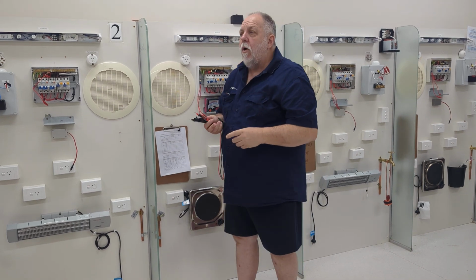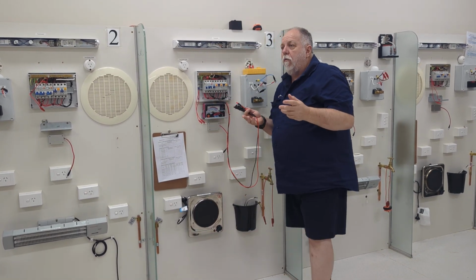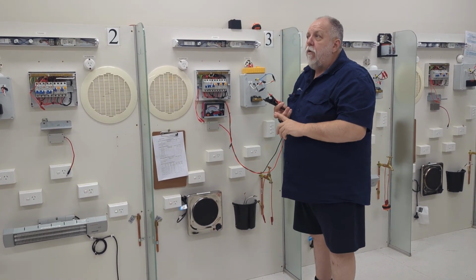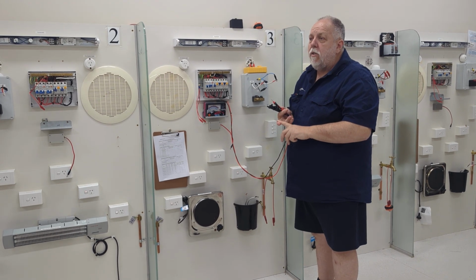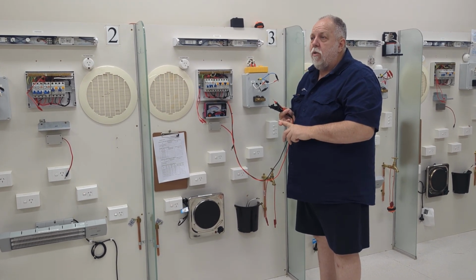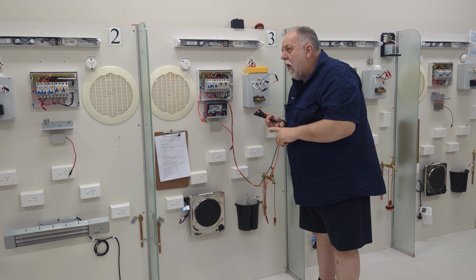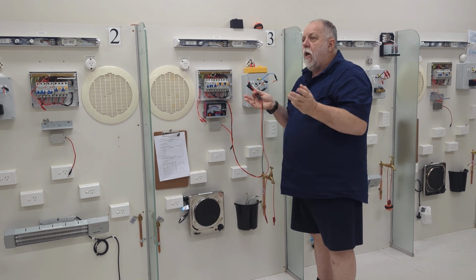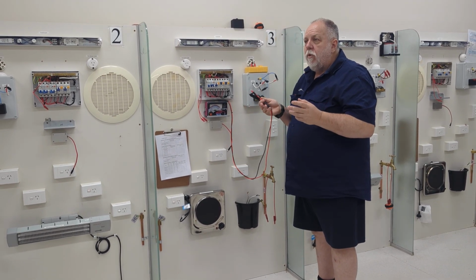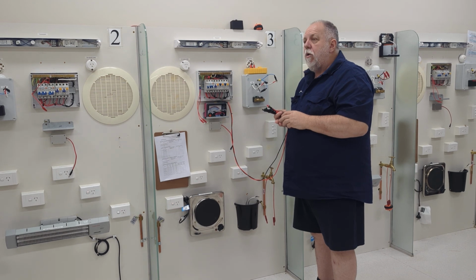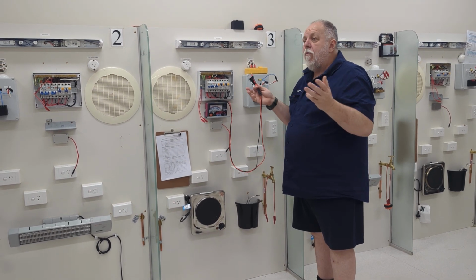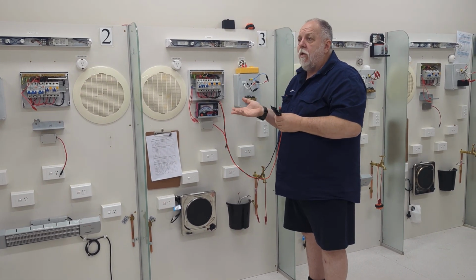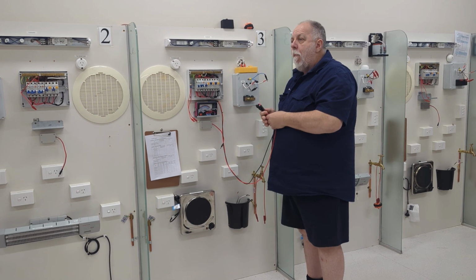Things that could also be in a lighting circuit is what? What other faults could I have? If you've got fluoros with ballasts and capacitors, they're ones that create shorts. Most LED lights these days, they don't normally create a short, they just go open circuit or don't work. So you'll find that it could be either crook wiring or something like that, but if we have LED lights and appliances removed, then it has to be somewhere in the wiring.